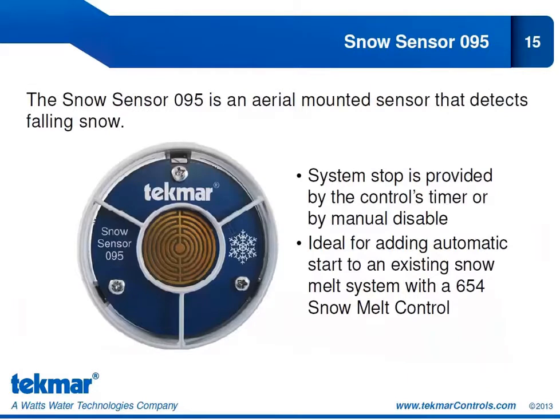Now our newest sensor: the snow sensor 095. This is an aerial mounted sensor that can detect falling snow, giving you automatic start and timed stop operation. The stop is provided by the 654's internal timer — once that time has expired, the snow melt system returns to its off state. This is a great way to add automatic operation to an existing snow melt system, but you must use the 654 snow melt control. You cannot connect the 095 to tekmar's other snow melt controls.